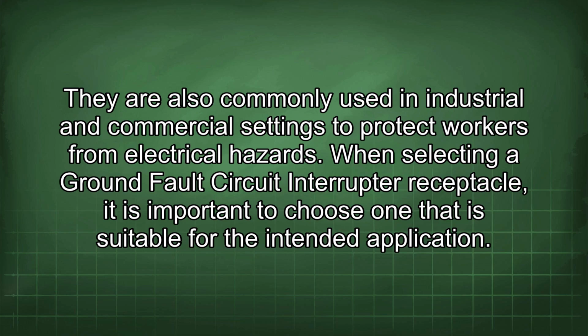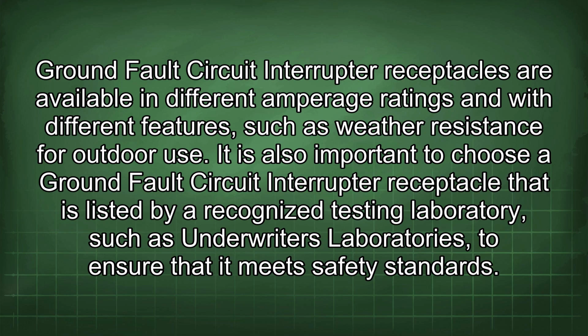When selecting a ground fault circuit interrupter receptacle, it is important to choose one that is suitable for the intended application. Ground fault circuit interrupter receptacles are available in different amperage ratings and with different features, such as weather resistance for outdoor use. It is also important to choose one that is listed by a recognized testing laboratory such as Underwriters Laboratories to ensure that it meets safety standards.